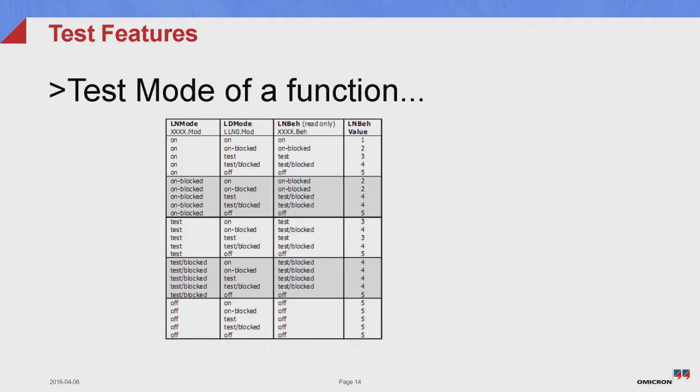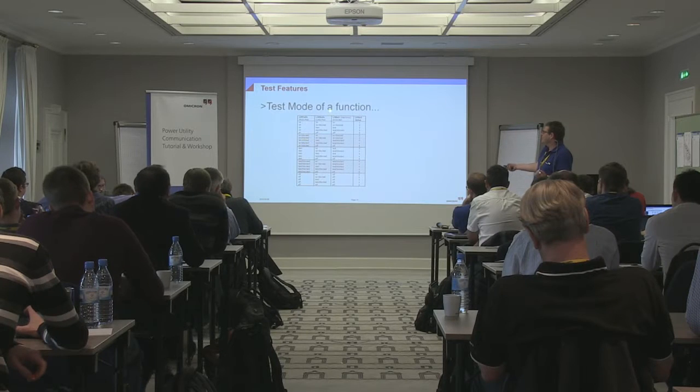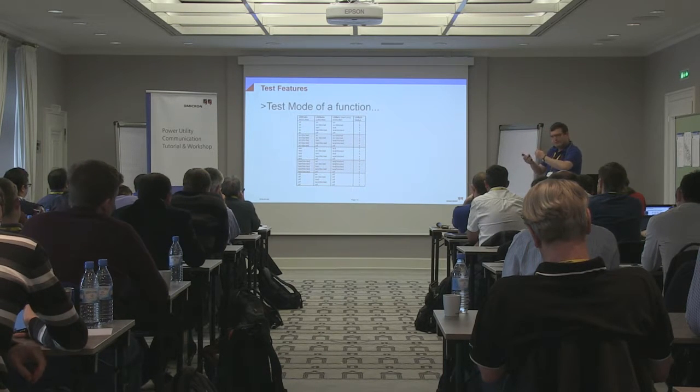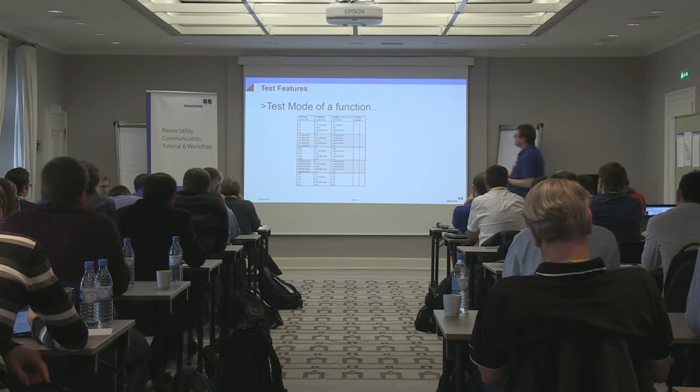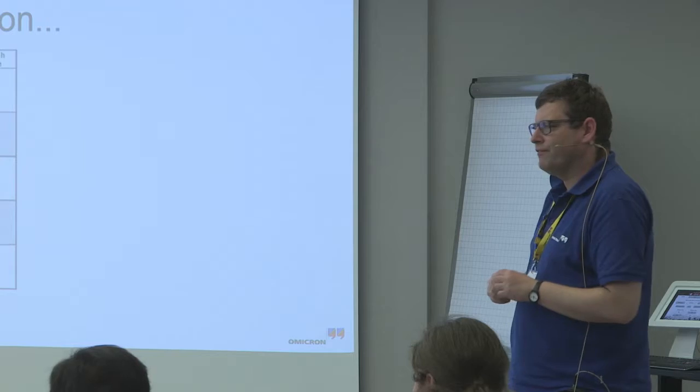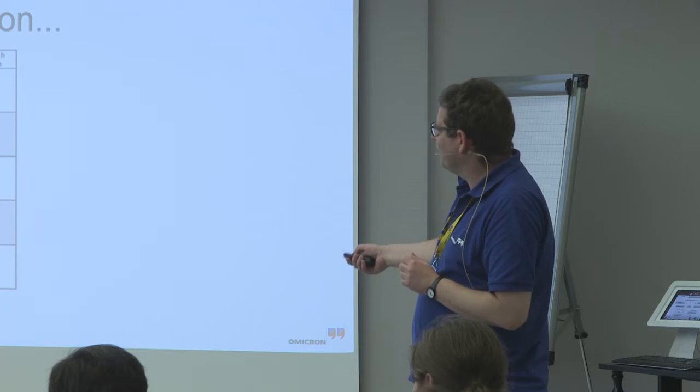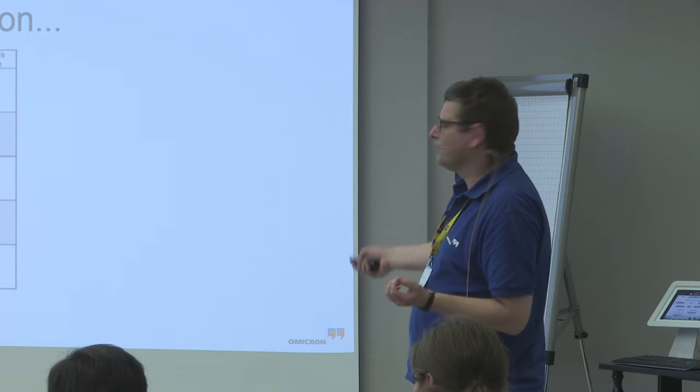When we have a look, and just for your reference to show you how it is defined in the standard, you can do it for the single node, and as well for the entire logical device, and then there might happen a resulting behavior, as they call it. So of course, if, for instance, the logical node is in test mode, and the device itself is kept on, then the resulting behavior should be test.